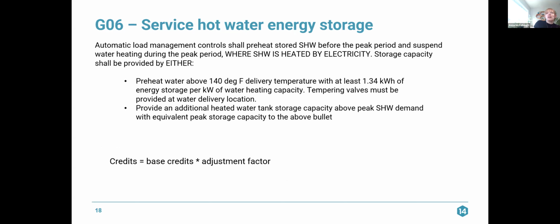Service hot water energy storage is where we are providing additional service hot water storage to reduce our peak service hot water demand. So automatic load management controls shall preheat stored service hot water before the peak period and suspend water heating during the peak period where service hot water is heated by electricity. The storage capacity shall be provided by one of two options: either preheating the water above 140 degrees delivery temperature with at least 1.34 kilowatt hours of energy storage per kW of water heating capacity required. Tempering valves must be provided at each water delivery location, so you're not burning people. You have to provide an additional heated water tank storage capacity.